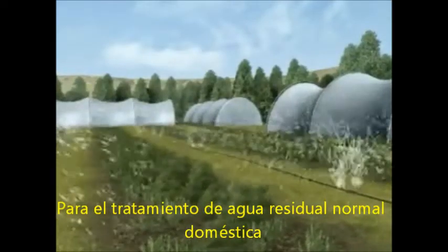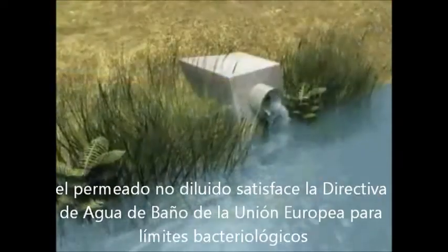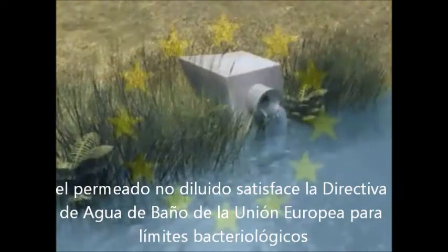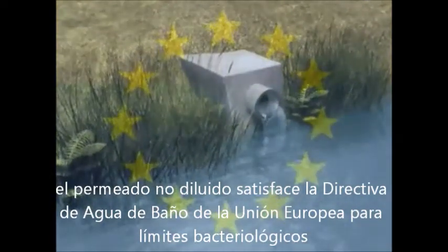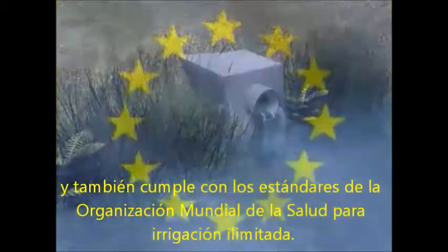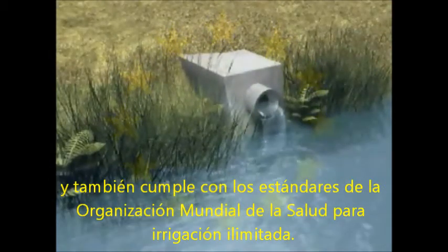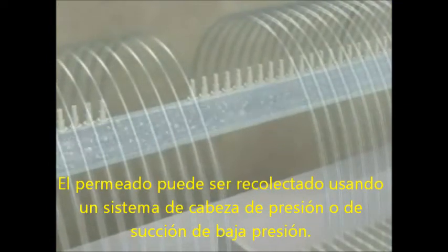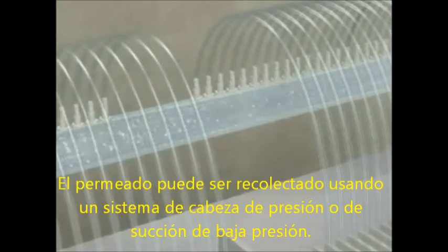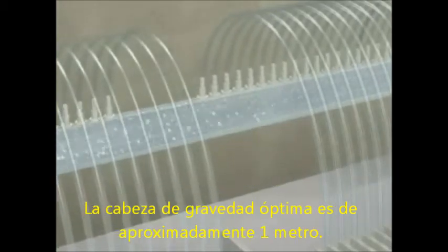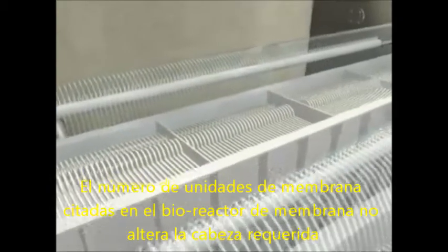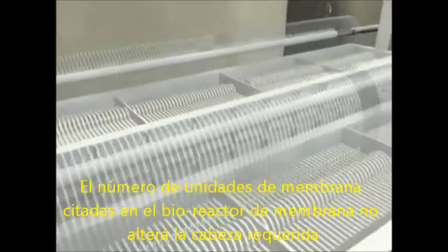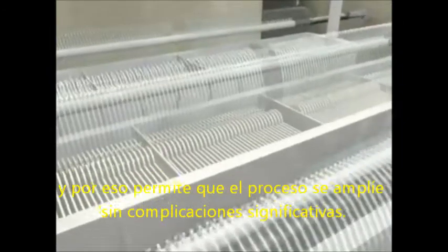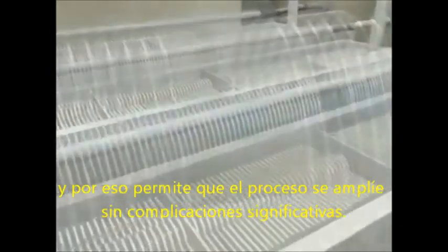For the treatment of normal domestic wastewaters, the undiluted permeate satisfies the European Union Bathing Water Directive for bacteriological limits and also complies with the World Health Organization standards for unlimited irrigation. Permeate can be collected either using gravity head or a low-pressure suction system. The optimum gravity head is approximately 1 meter. The number of membrane units sited in the membrane bioreactor does not alter the required head, thus enabling the process to be scaled up without any significant issues.